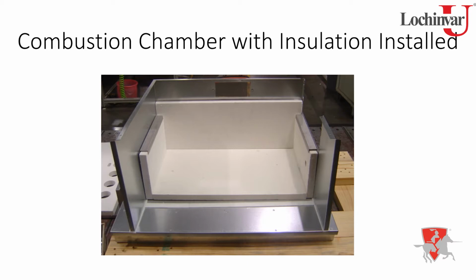Back when I was in our tech service department, I had a gentleman call in. I believe it was on a copper fin tube, but realistically, the copper fin tube and this unit, the EnergyRite, are all going to be serviced the same way. This gentleman took his burners out. He was doing a cleaning and wanted to clean up his heat exchanger as well. So he took a pressure washer to the heat exchanger and absolutely soaked every bit of this refractory tile. Unfortunately, if this refractory tile gets soaked, it's going to start to break down.